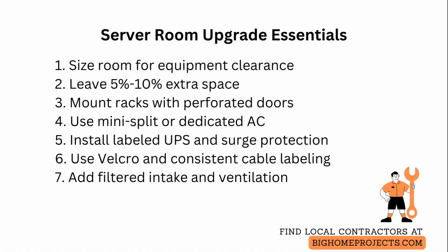Install a labeled uninterruptible power supply sized to run critical devices for the time you need during outages, and add whole house surge protection at the electrical panel to protect against voltage spikes. Use vertical and horizontal cable management, Velcro straps, and a consistent labeling scheme for both ends of every cable to cut troubleshooting time in half. Include filtered air intake and a simple ventilation path to prevent dust buildup, and consider a humidity control strategy so relative humidity stays between 30 and 50% to protect electronics.